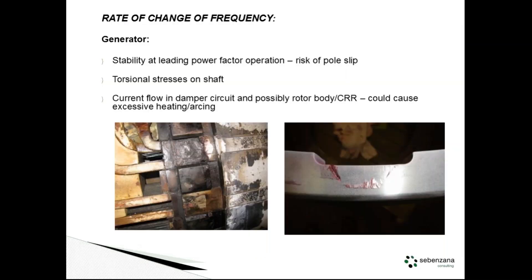Moving on to the rate of change of frequency. One of the issues is if the system frequency changes too fast, the generator can't keep up — the ability of the generator to maintain synchronicity can't keep up. You've heard of pole slipping: not good, potential tripping out of the generator itself or the auxiliaries, and you lose a big machine and then have problems getting back onto the grid. What we're probably more concerned with for long-term damage is torsional stress on the shaft — as you're trying to ramp up and down the frequency, increasing and decreasing speed, you're effectively twisting the shaft.